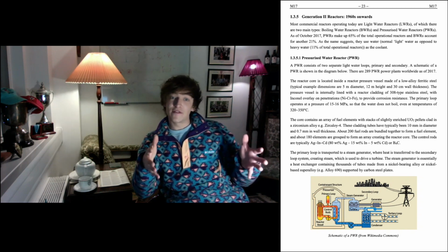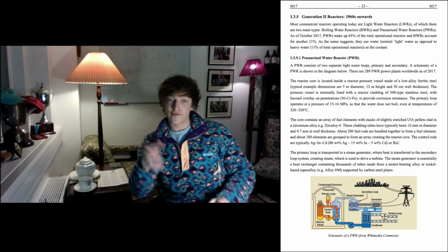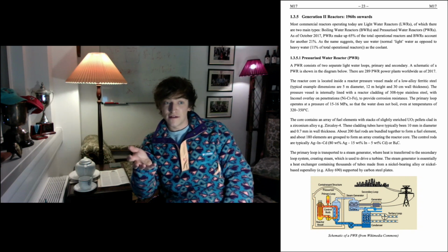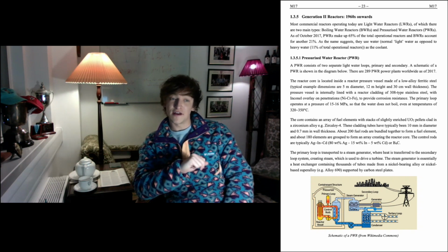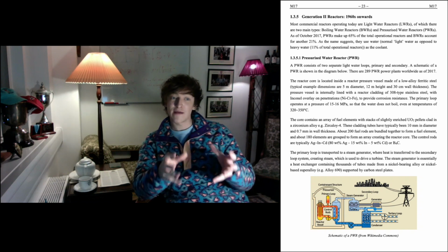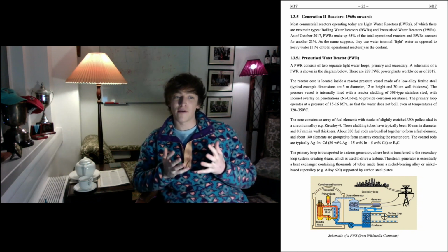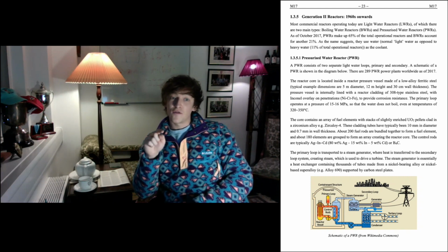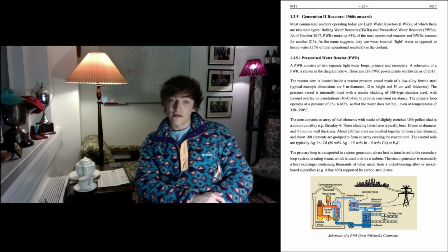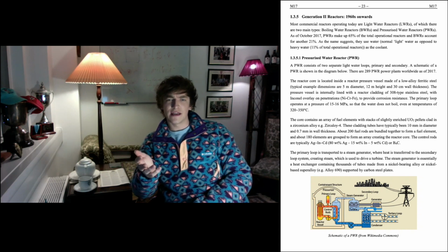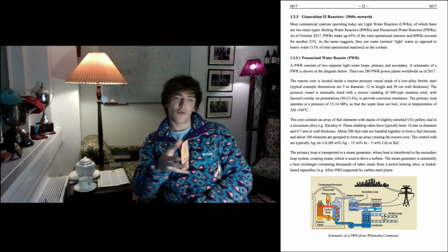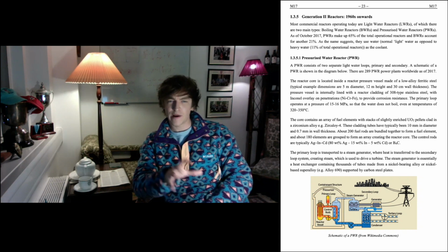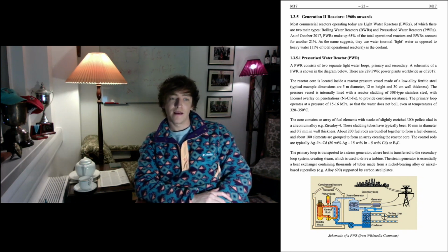And within those elements, you've got channels for the coolant to travel to get that heat out of the fuel. And in this case, we've got light water, which also serves as our moderator. So light water is the coolant, but it also slows down the neutrons to allow fission to occur. You're also going to have channels for the entry of the control rods. And those control rods are typically silver, indium, cadmium alloy, or they can be boron carbide, and they're clad in, for example, stainless steel. And we'll talk about control rods again in more detail later on.